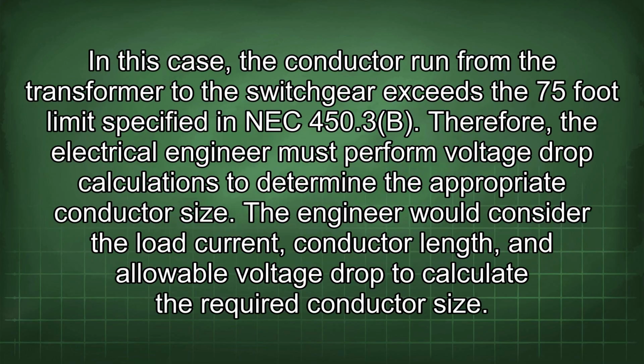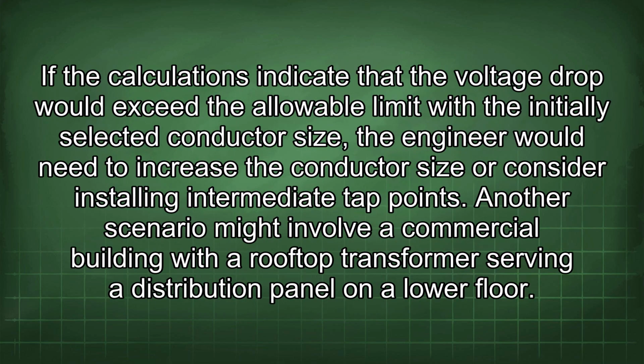In this case, the conductor run from the transformer to the switchgear exceeds the 75-foot limit specified in NEC 450.3(b). Therefore, the electrical engineer must perform voltage drop calculations to determine the appropriate conductor size. The engineer would consider the load current, conductor length, and allowable voltage drop to calculate the required conductor size. If the calculations indicate that the voltage drop would exceed the allowable limit with the initially selected conductor size, the engineer would need to increase the conductor size or consider installing intermediate tap points.